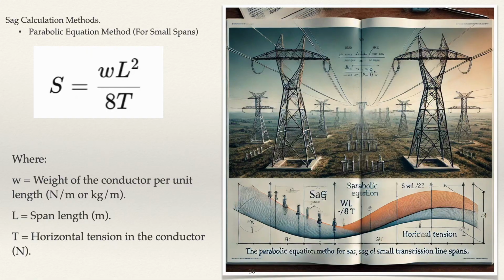Sag calculation methods. There are two primary methods for calculating sag. 1. Parabolic equation method for small spans. This method assumes the conductor forms a parabola, which is accurate for spans less than 300 meters. The sag S can be calculated using the formula, where W equals weight of the conductor per unit length, N/m, L equals span length, m, T equals horizontal tension in the conductor, N.